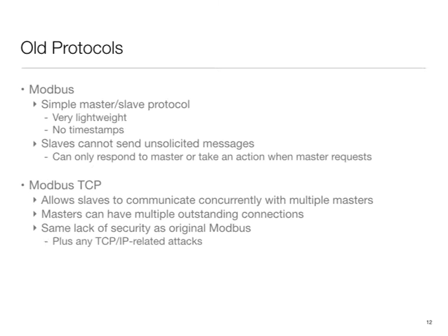What changed in recent times is that a lot of these systems migrated to sending Modbus type data, but over TCP/IP. So what you see now increasingly is that either they will have Ethernet interfaces, or you can buy so-called serial servers. They talk to your, let's say, smart meter using a serial device, and on the other side they have a standard TCP/IP interface, and then now you're in the world of our regular internet-style communication. So Modbus TCP is out there, and in fact there are lots of apps.